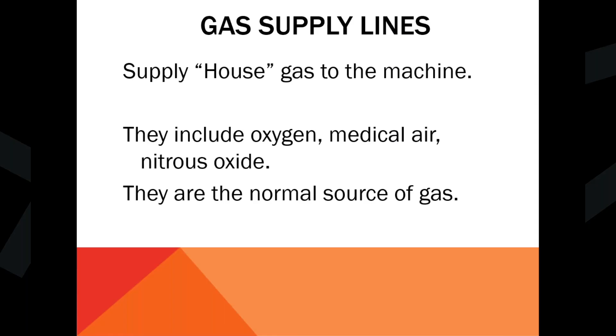And here's a manifold showing your gas. Here's your nitrous oxide, your medical air, your oxygen, and then you have your vacuum, and this should be your waste anesthesia gas. It's kind of interesting why that's not hooked up. And then here's where they would plug in, this being a boom, and then the wall. You have your medical air, 2 oxygens, your waste anesthesia gas, and then your nitrous oxide.